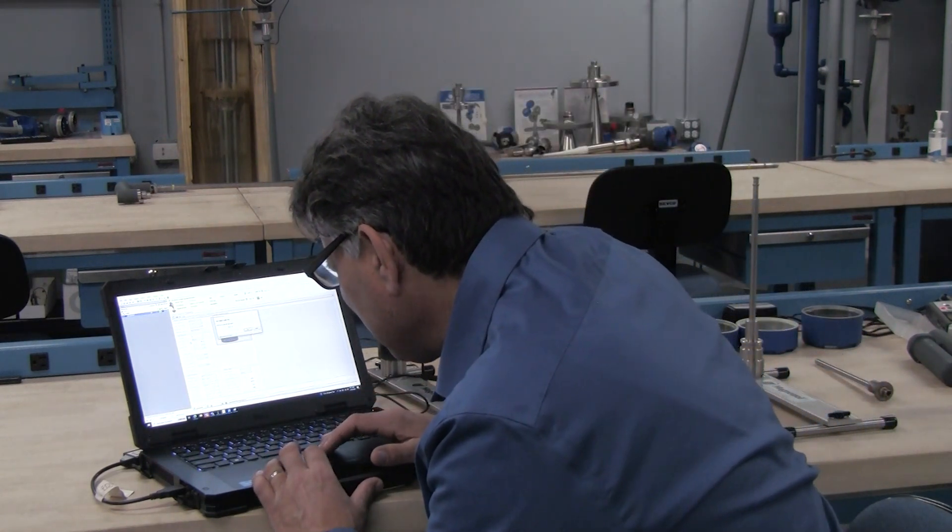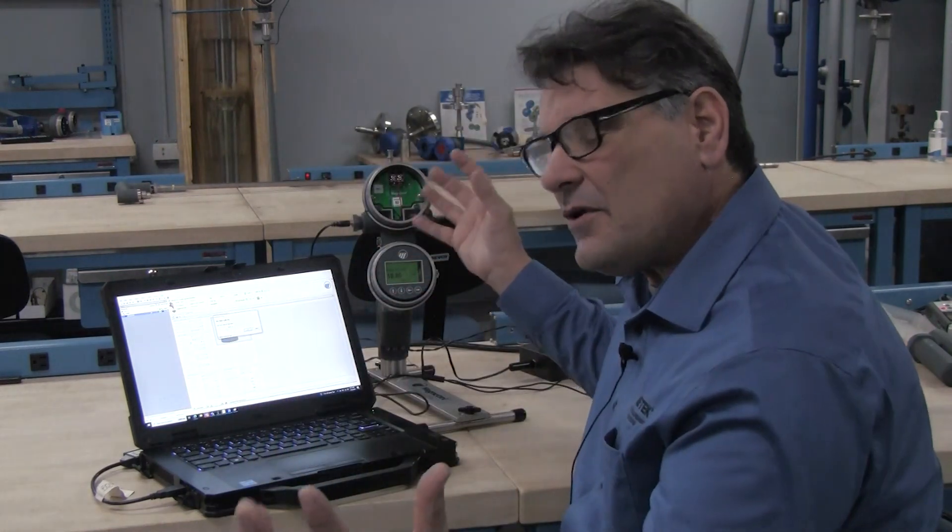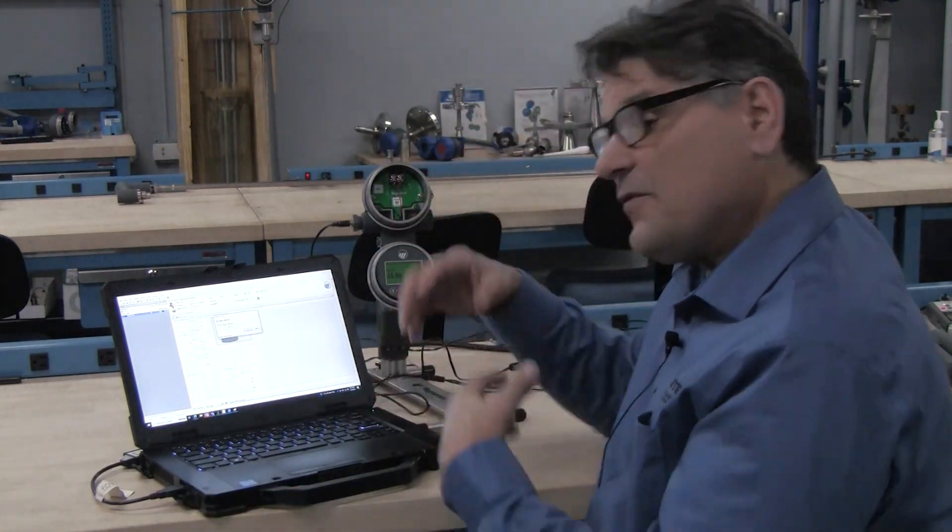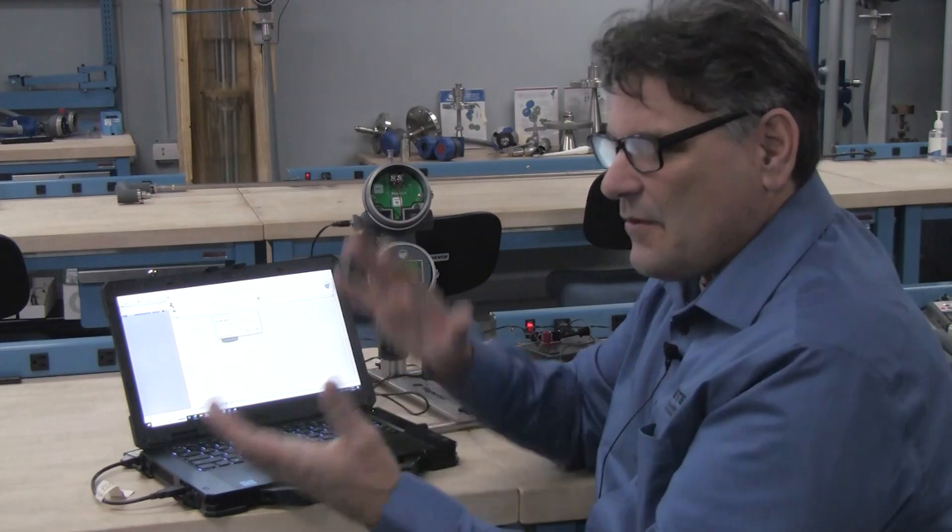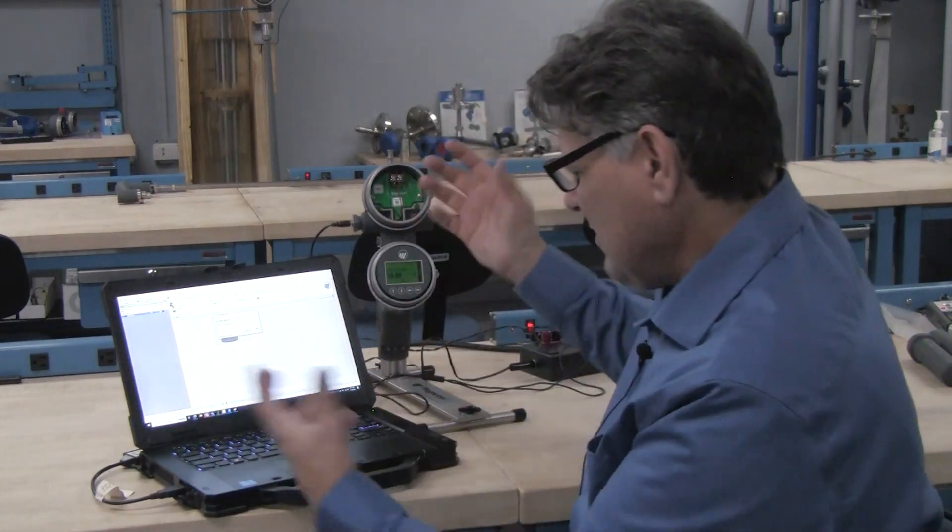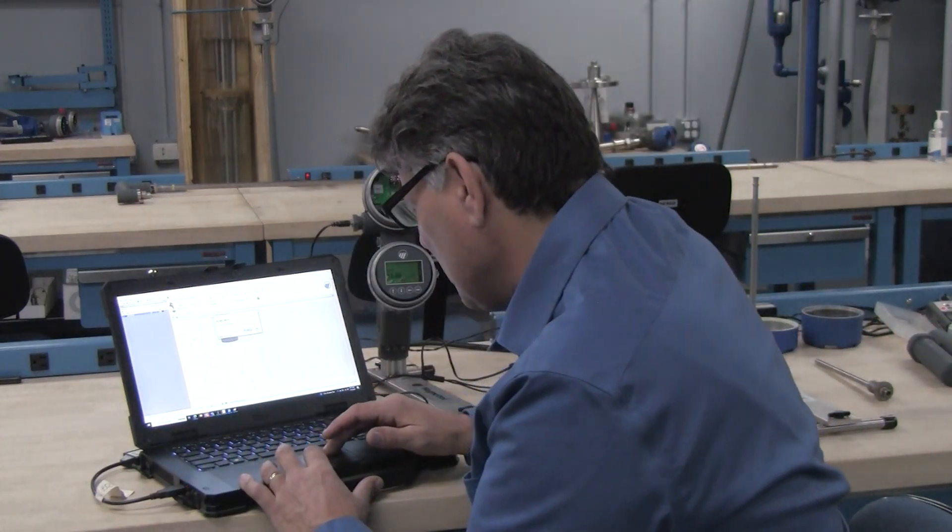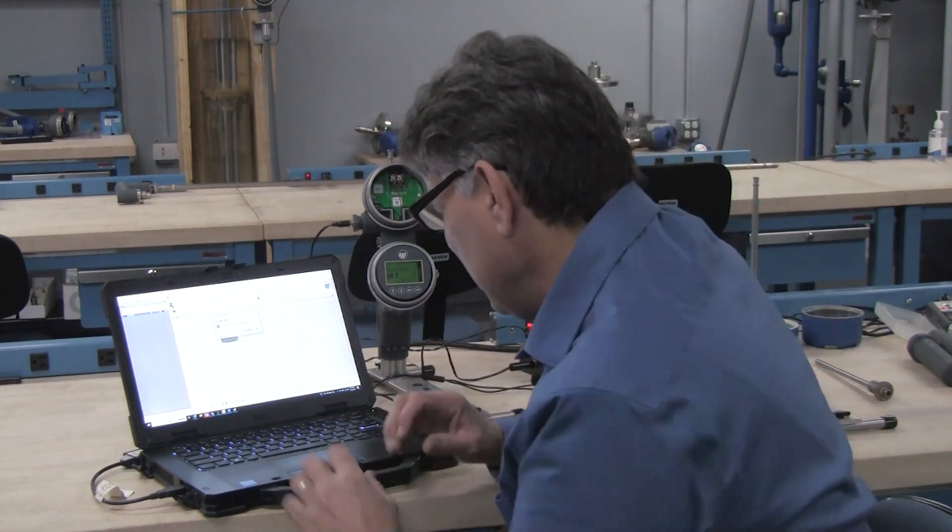And I'm going to enter that. And I'm going to call that whatever level I want to associate that with. So if it was like the displacer I showed you earlier, that was a 14 inch displacer. My high point, I'm going to call it 14 inches. Enter that.